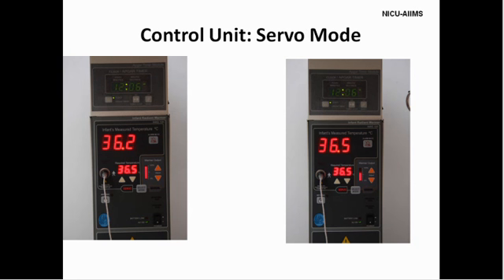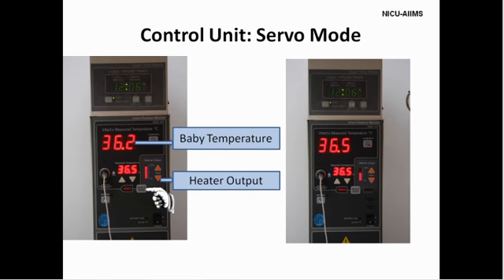The control unit has a mode selection button, a knob or a switch to decrease or increase the heater output, and the alarm silence button. In addition, the control panel also displays the patient's temperature, the control or the set temperature, and the heater output. Most of the warmers function in two modes: the servo mode or the automatic mode or the baby control mode, and the manual mode. In the servo mode, the heater output is regulated by the infant's skin temperature.